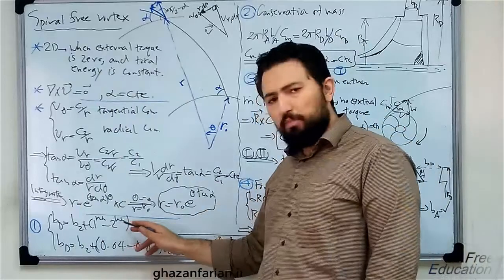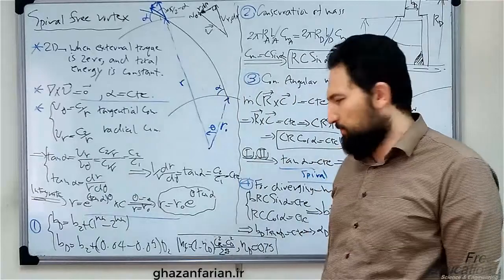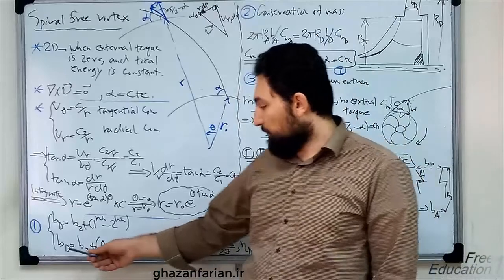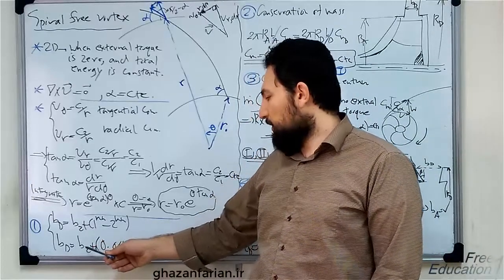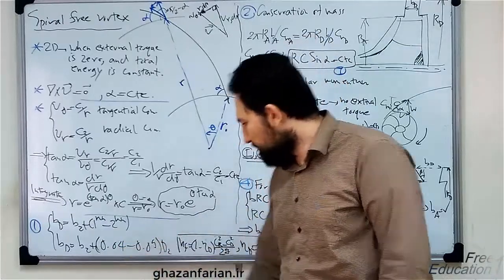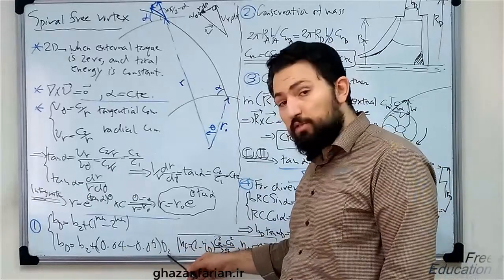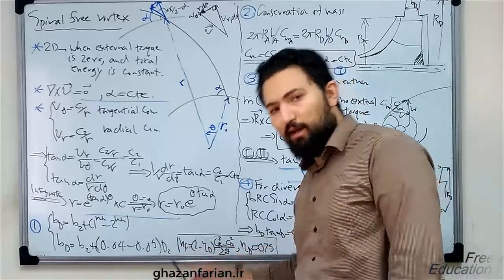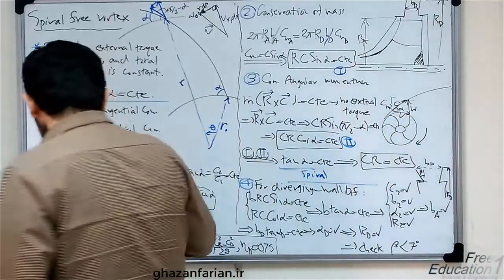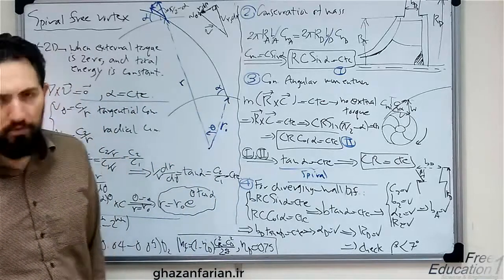One millimeter to two millimeters larger than the width of the blades at the outlet is a good suggestion. The second relation indicates that the width of the diffuser equals the width of the blades at the outlet plus 4% or 5% of the diameter of the impeller at the outlet. Both of them can be used, and this way you have computed the first geometrical parameter of the diffuser.